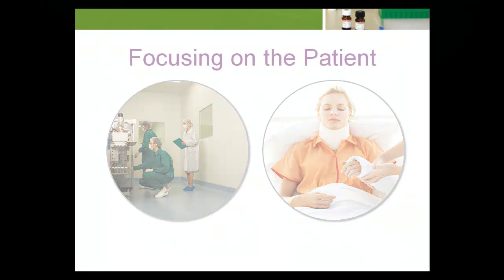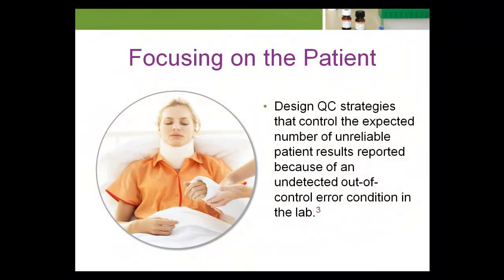Laboratories tend to design QC strategies with a focus limited to controlling the state of the instrument rather than controlling the risk of producing and reporting unreliable patient results that could compromise patient care. One approach that more directly focuses on the quality of patient results, rather than the state of the instrument, is to design QC strategies that control the expected number of unreliable patient results reported because of an undetected, out-of-control error condition in the lab.